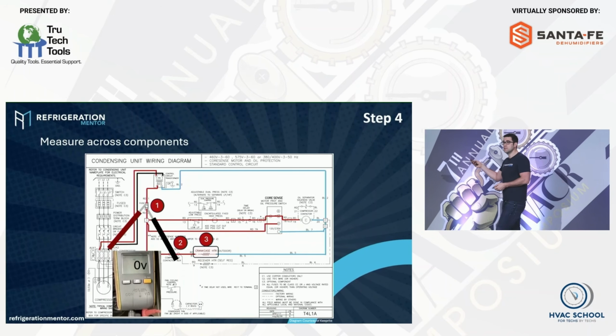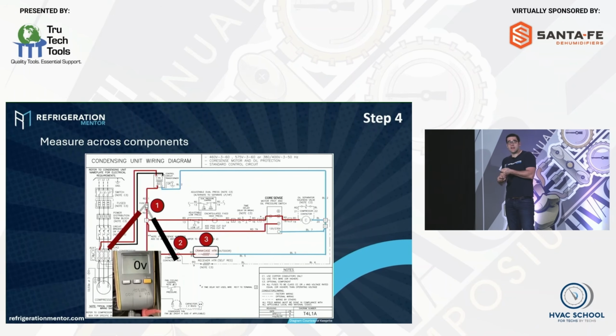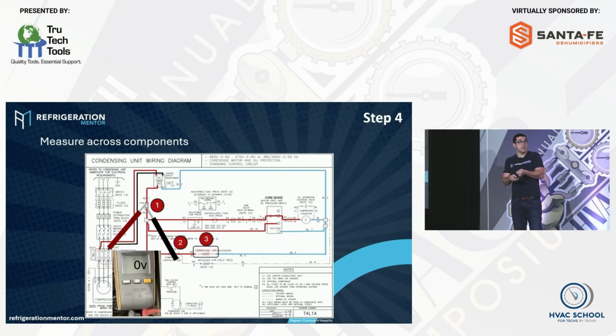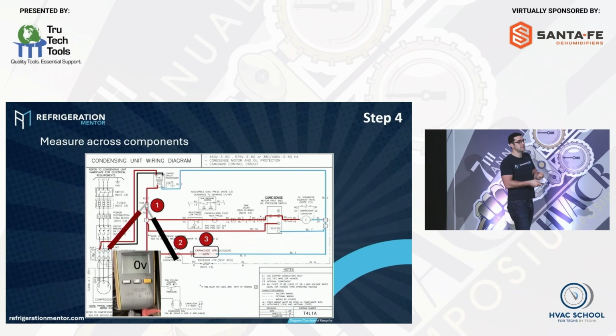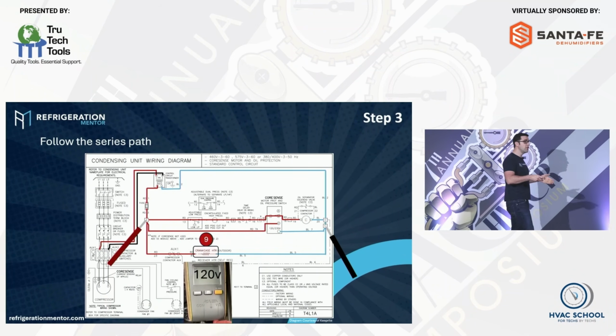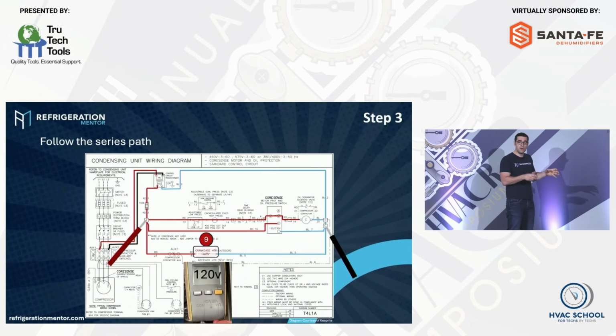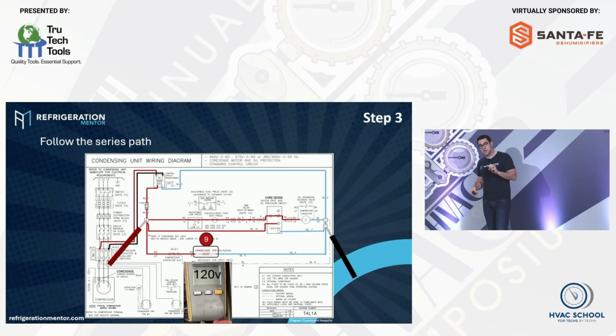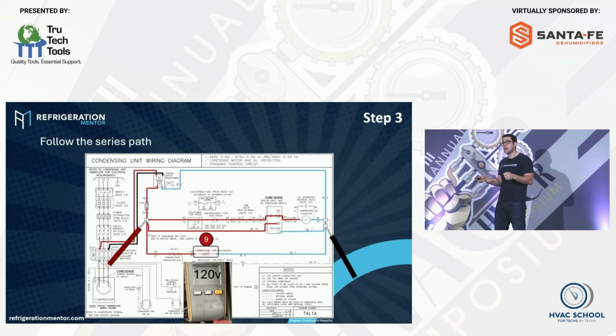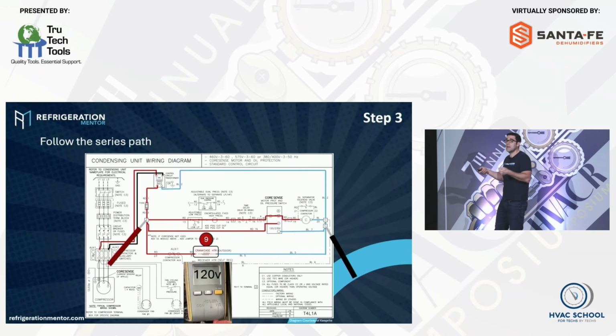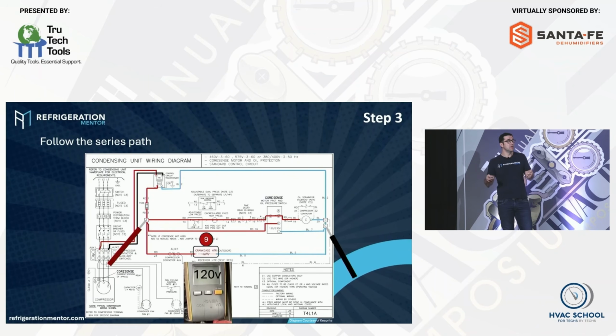This here is a fuse. If I measure across the fuse and I get 0 volts, that fuse is good. If I measure across and I get 120 volts, that means it's open. Okay, follow the path. Now, instead of me pulling off the covers of the low pressure switch or the high pressure switch or anything, I go across it. Do I got voltage? I got voltage across it.